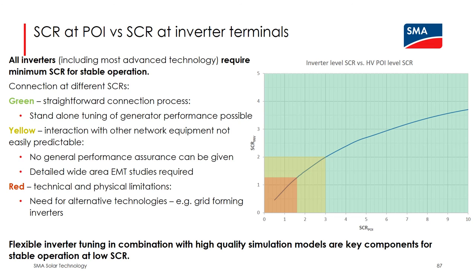When going lower with the SCR, so that would be the yellow range here, going down from 3 maybe to roughly 1.6, this is the range where most of the Australian projects are. There are actually good chances that some kind of interaction with other network equipment is possible, but definitely not easily predictable during the generator design process. To really work this out, detailed wide area EMT studies are required, which can highlight what kind of interaction or additional effects have to be considered and then can be addressed via the generator tuning process.